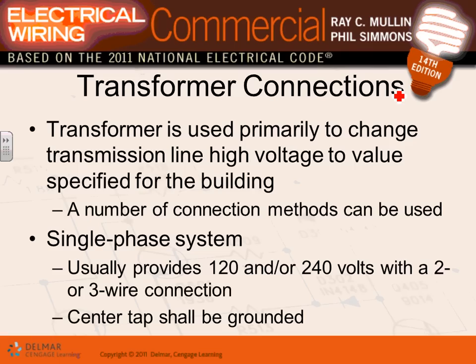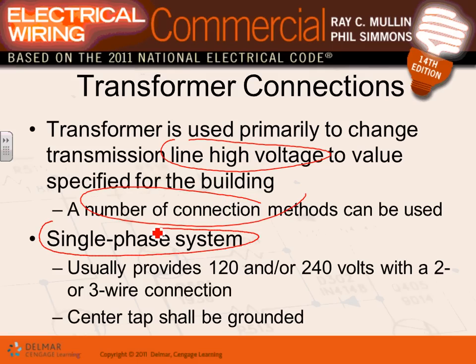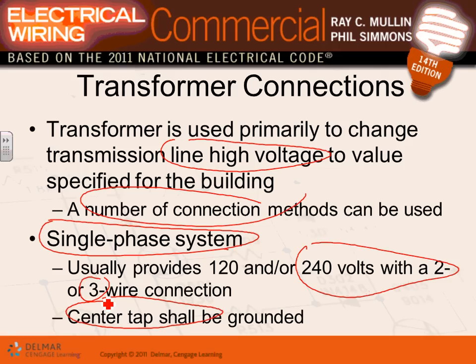Okay, so we have transformers used primarily to change the transmission high voltage. That's what we do in the building. Take the high voltage, transform it down to utilizable voltages. There are a lot of connections, guys, that we went through some of them. The single most important one that we did in the residential project was the single phase. It can give you this voltage, 3-wire actually, 240/120. That's the most important one. The center tap of this transformer is always the grounded one.